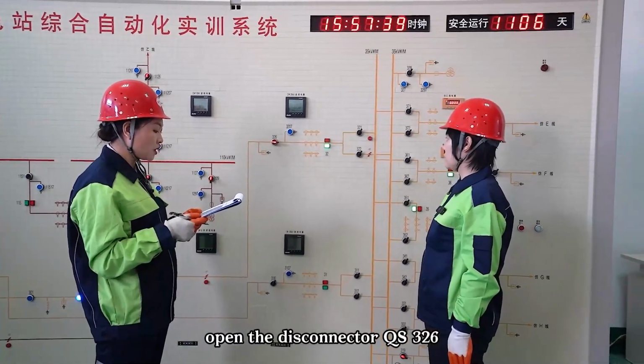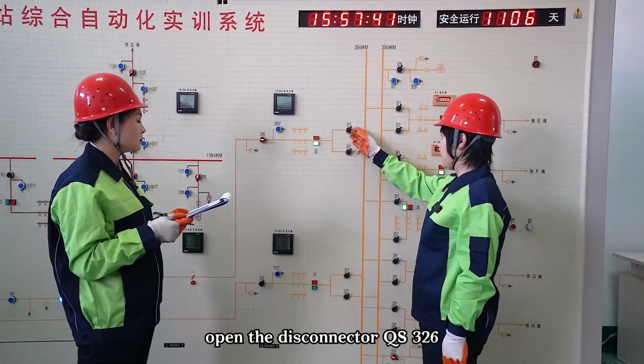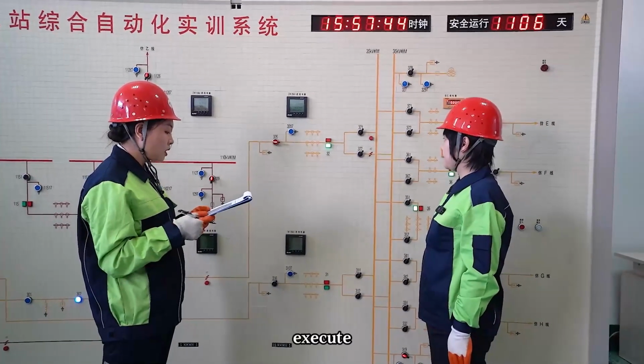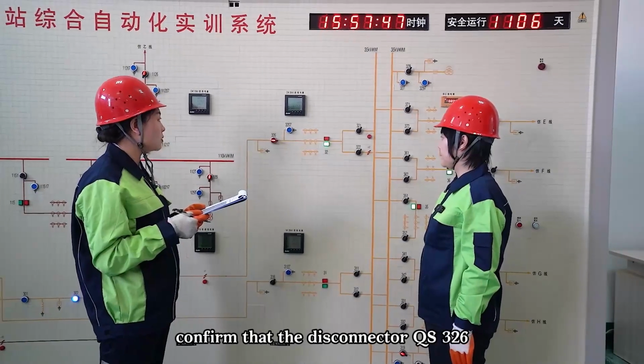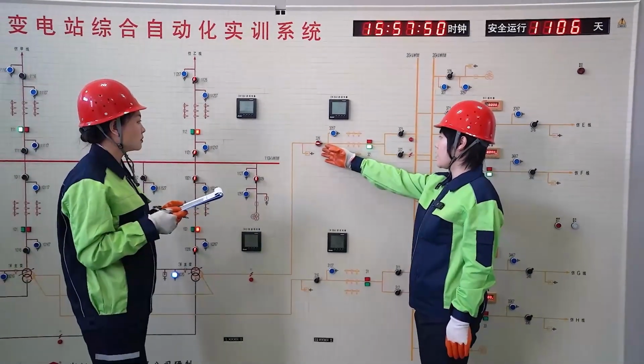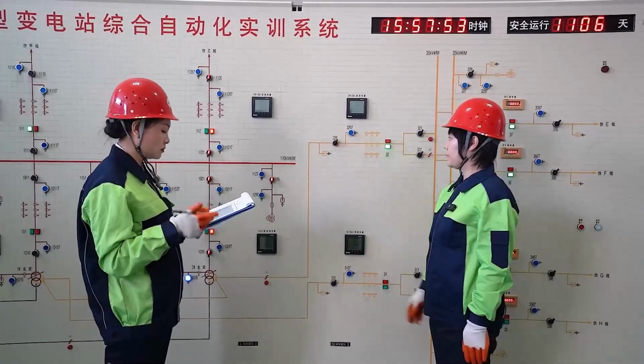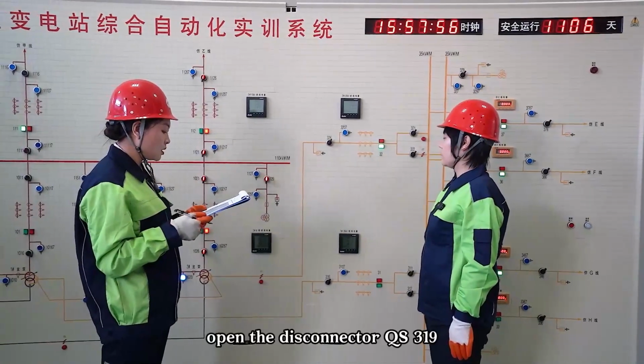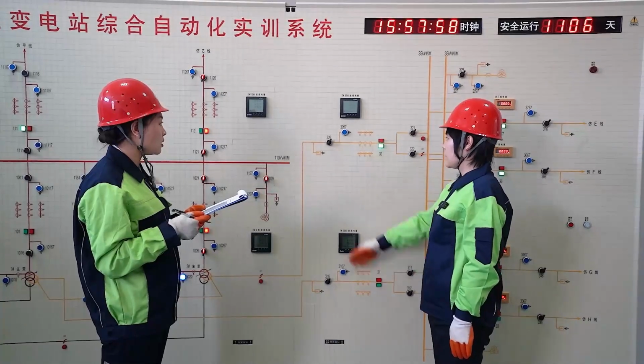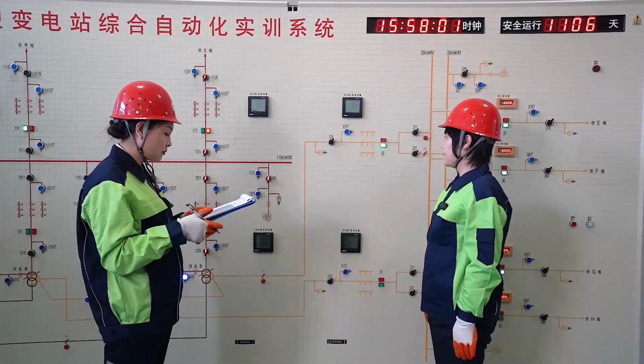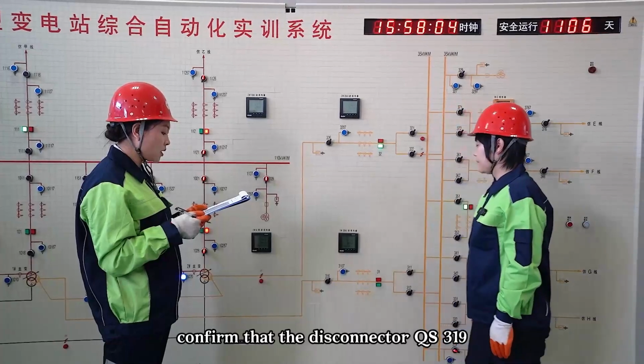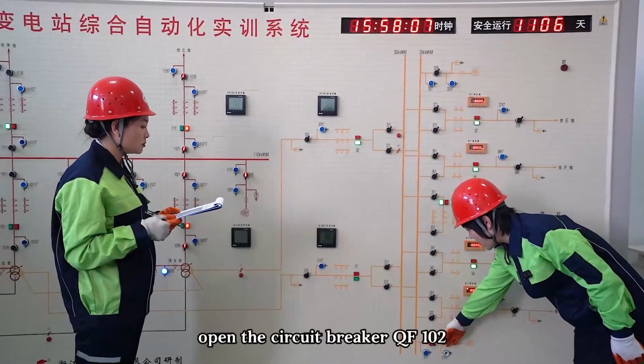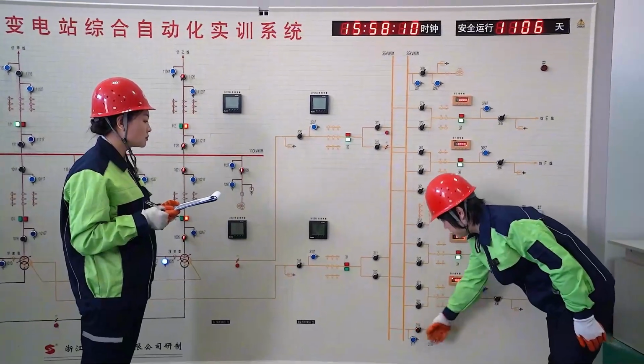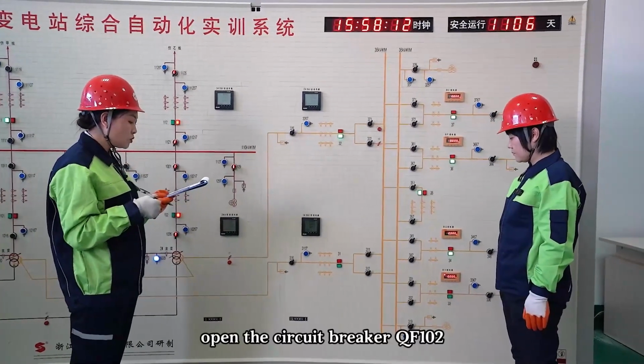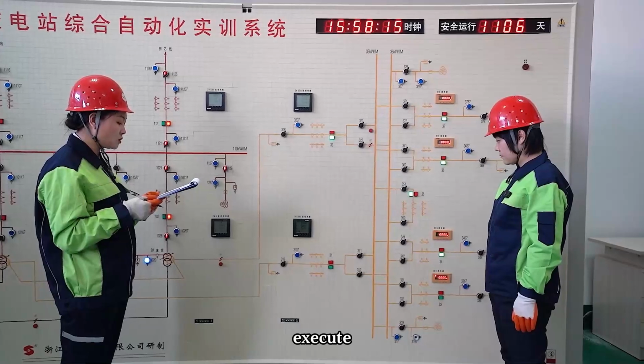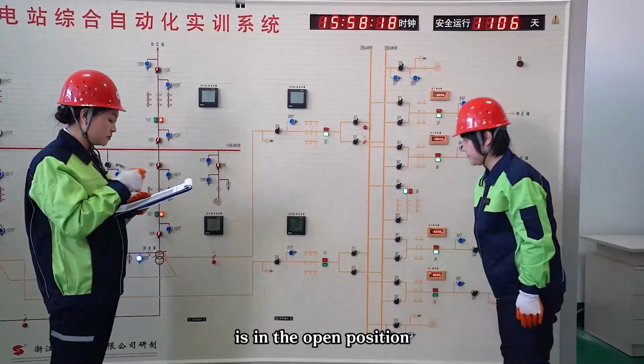Confirmed. Open the disconnector QS326. Execute. Confirm that the disconnector QS326 is in the open position. Confirmed. Open the disconnector QS319. Execute. Confirm that the disconnector QS319 is in the open position. Confirmed. Open the circuit breaker QF102. Execute. Confirm that the circuit breaker QF102 is in the open position.